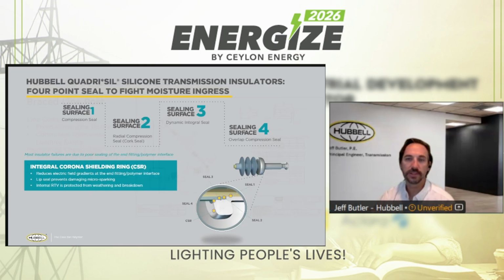And then I'll kind of finish with these last couple slides of the Quadrisil design. So I refer to this as our latest generation of polymer insulator. It refers to the redundant sealing system of the geometry of the end fitting and the rubber. So quad refers to similar to 4 redundant seals that are used, as well as a corona shielding ring, or this larger donut piece that is part of the metal end fitting. And as I mentioned, Hubbell had success in the performance of our insulators even in the 70s and 80s because we've always had a design that includes this corona shielding ring. So this larger ring helps to distribute those electrical stresses right at that interface of the end fitting and the rubber where it all comes together. So having that piece on our initial designs, even back in the 70s and 80s, helped improve the performance of our insulators. We maintain that design even today as having the largest corona shielding ring integral or as part of our end fitting of any manufacturer on the market today.